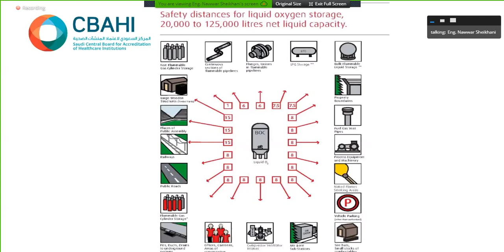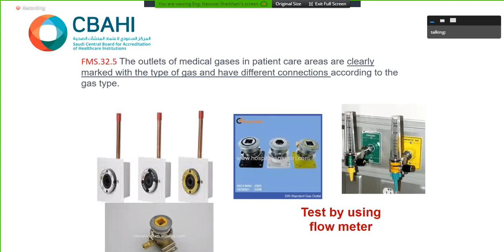32.5, the outlets of medical gas are clearly marked with the type of gas and have different connections. Actually, we recommend in CBAHI to use the DIN standard, I mean the German standard, in choosing the outlet, where there is no chance to install a probe in a wrong outlet. However, once we visit hospitals, we check the marking of the outlets, and we ask the nurse to test the gases by using flow meters, suction, oxygen, etc.